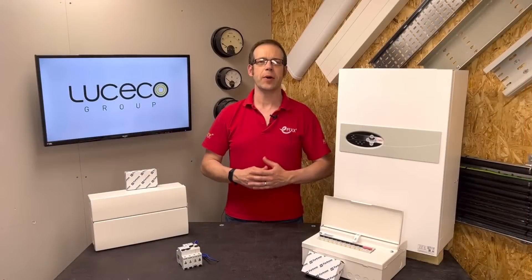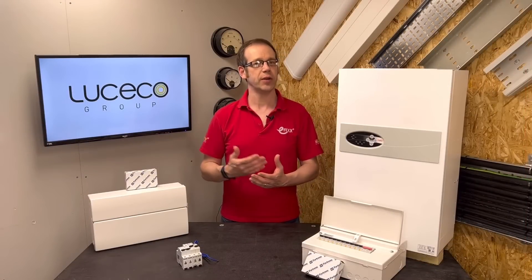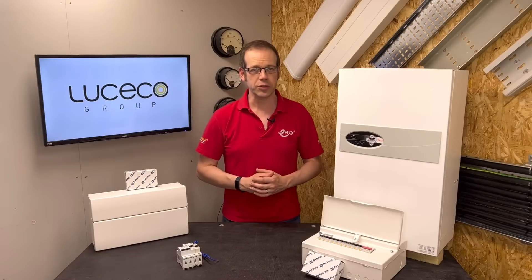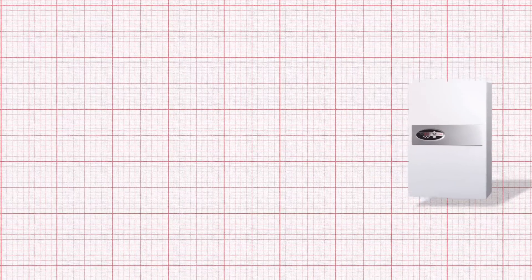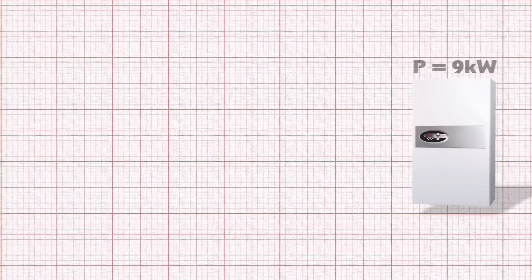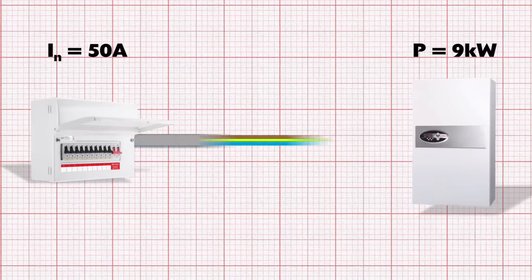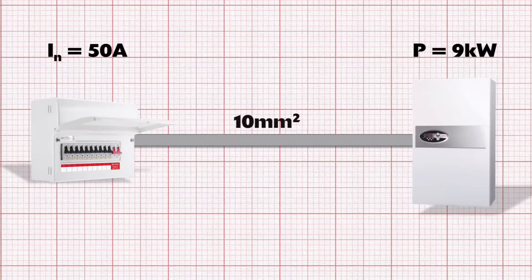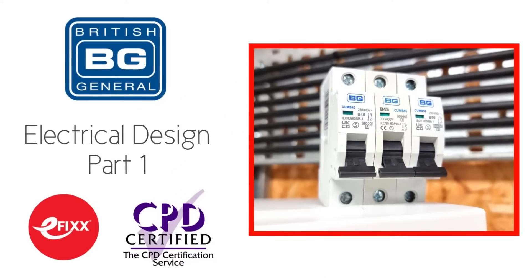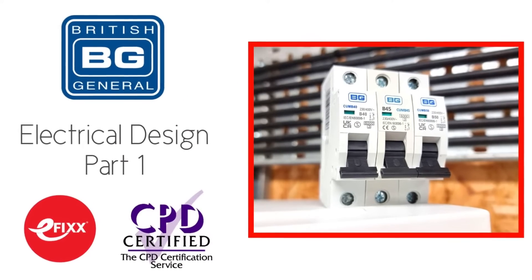As this is part two of the electrical design package, and it may have been a while since you looked at the previous one, we'll do a quick recap on the scenario and numbers we're working with. We're carrying out the design of an electrical circuit feeding a 9kW Fusion Comet Electric boiler from the Electric Heating Company. We're using a 50A Type-B MCB from the Fortress range by BG Electrical to protect the 10mm² twin and CPC cable. If you're interested in how we arrived at these values, please go and check out part one, as it will help your understanding of the next steps in the design process.